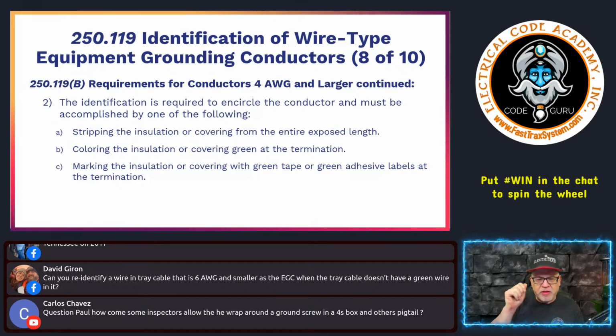Now, the guys that do things in the code, we see this all the time, even for identification of ungrounded hot conductors and re-identifying conductors in a cable assembly, where you can reuse the white as a hot conductor only in cables. Not in raceways, but in cables. There is an allowance in 200.7 for you to do that.